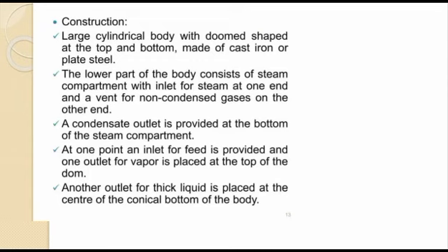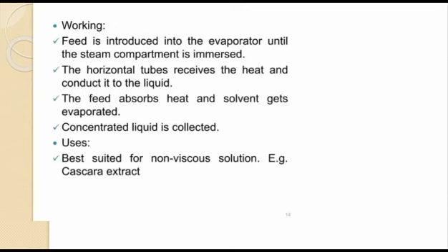Construction: a large cylindrical body with a dome shape at the top and bottom, made up of cast iron or plate steel. The condensate outlet is provided at the bottom of the steam compartment. At one point, an inlet for feed is provided. An outlet for vapor is placed at the top of the dome. Another outlet for thick liquid is placed at the center of the conical bottom of the body.